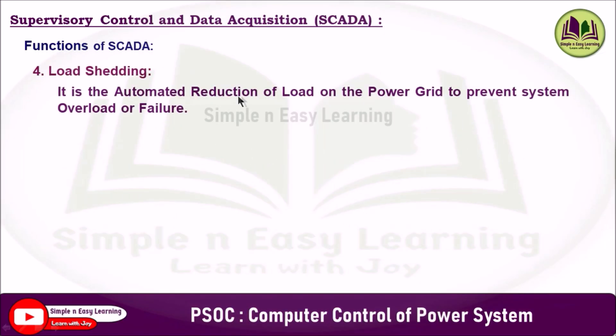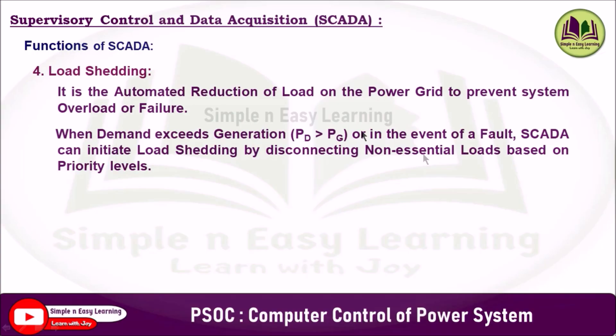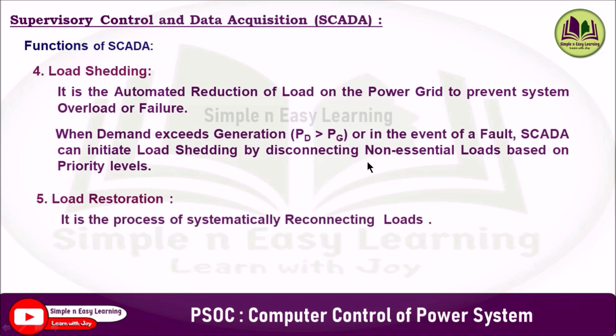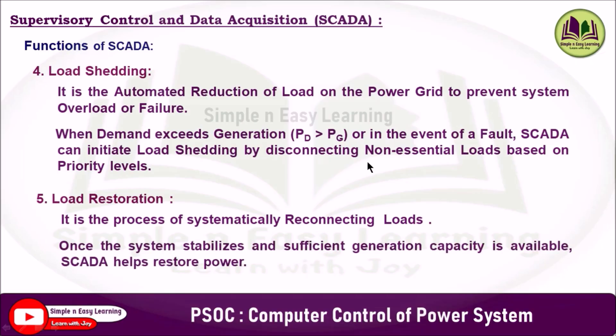The fourth function is load shedding — an automated reduction of load on the power grid to prevent system overload or failure. When demand exceeds generation or a fault occurs, SCADA can initiate load shedding by disconnecting non-essential loads based on priority levels, helping maintain grid stability and prevent widespread blackouts. The fifth is load restoration, a process of systematically reconnecting loads previously shed during a disturbance. Once the system stabilizes, SCADA restores power to affected areas following predefined priorities, ensuring a safe, efficient and orderly recovery while minimizing downtime.